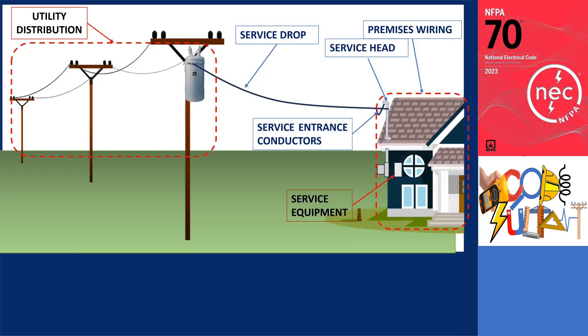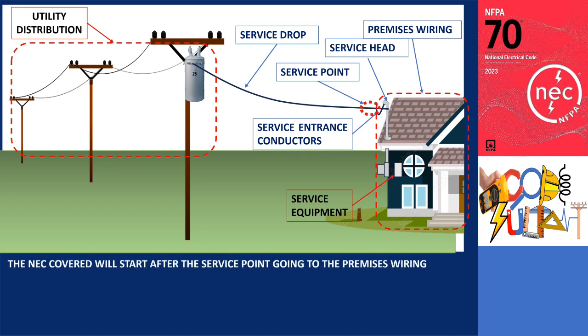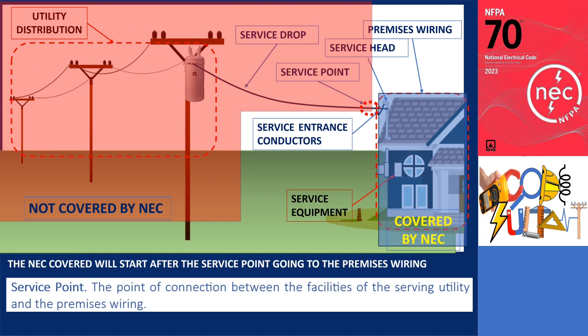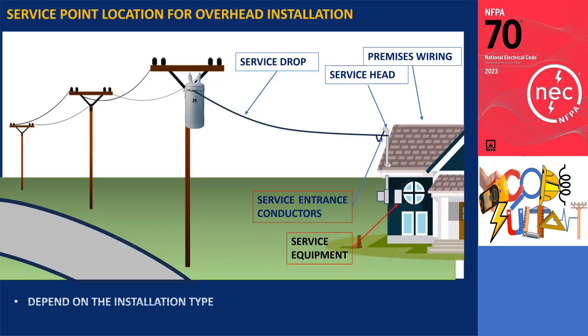The NEC coverage will start after the service point going to the premises wiring. The service point is defined by the code as the point of connection between the facilities of the serving utility and the premises wiring. The positioning of the service point is subject to variation based on the specific installation type, with the electrical utility typically determining its location.